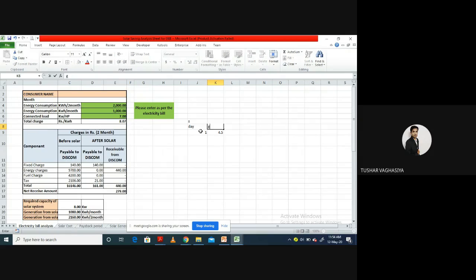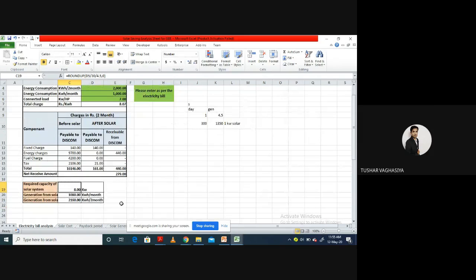This is the thumb rule based on solar radiation available in Gujarat. Considering 300 days per year, 1 kilowatt of power generates 300 multiplied by 4.5, approximately 1350 units per year for 1 kilowatt. That's how much energy a 1 kilowatt solar system generates. Based on this calculation, I've derived that you need an 8 kilowatt solar power plant.